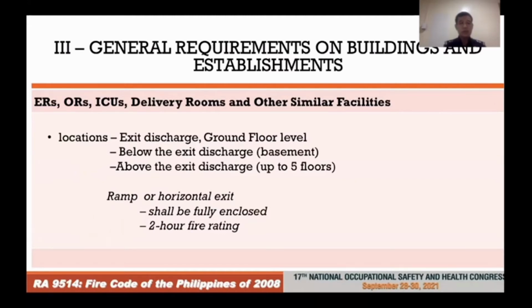So again, the general rule is still that it should be on the ground floor. However, if for any reason you cannot use the ground floor as the location of these facilities, you may locate it up to the 5th floor or up to the first level basement, provided that you provide a ramp or a horizontal exit. This ramp or horizontal exit must be fully enclosed in a 2-hour fire rating enclosure.